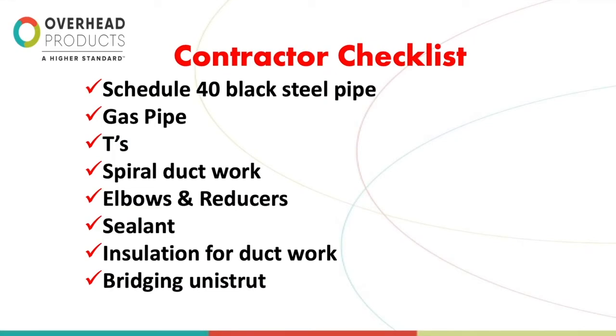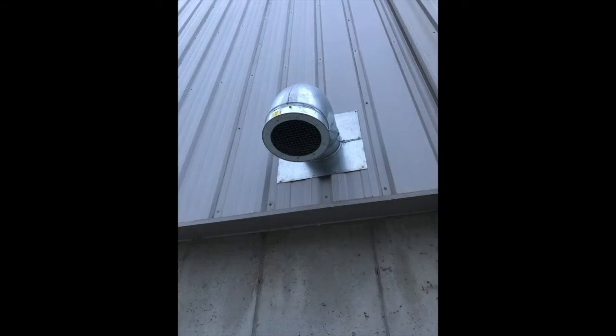Items that will need to be provided by the installing contractor are Schedule 40 black steel pipe. Please note that Schedule 40 pipe is a requirement and no substitutions will be allowed. Gas pipe, T's, spiral ductwork, elbows, reducers, sealant for the ductwork, insulation for the ductwork, bridging unistrut for attachment to the ceiling or wall to suspend the system. All combustion air ductwork will also need to be supplied by the installing contractor.